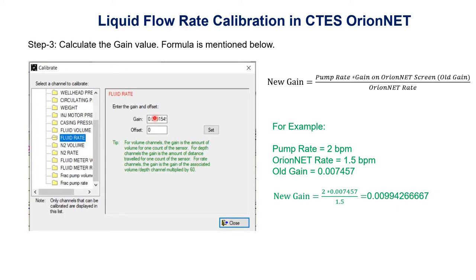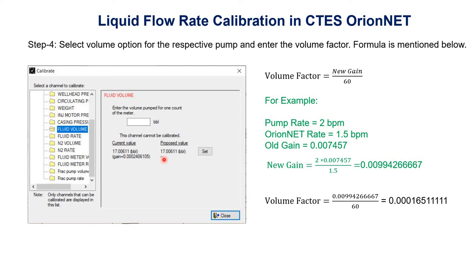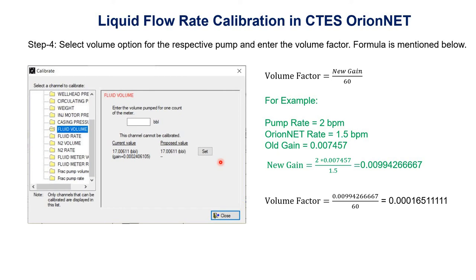We will put this new gain value of 0.009942 in the field and click the set button. Next, we need to calculate the volume factor for fluid volume. The formula for volume factor is: new gain divided by 60. So 0.009942 / 60 = 0.000165111. We enter this number in the volume cell, click set, and in this way our liquid flow rate is calibrated. Basically, we calculate two values: the new gain and the volume factor.